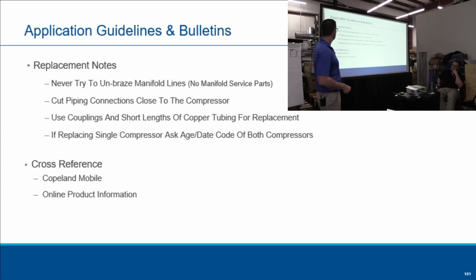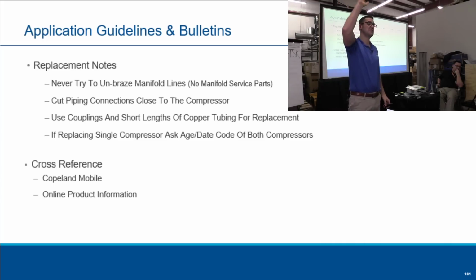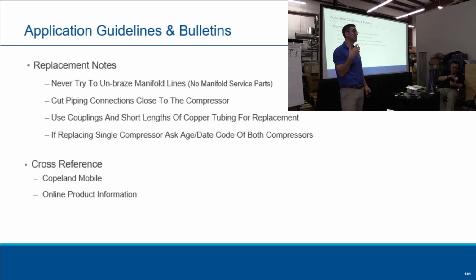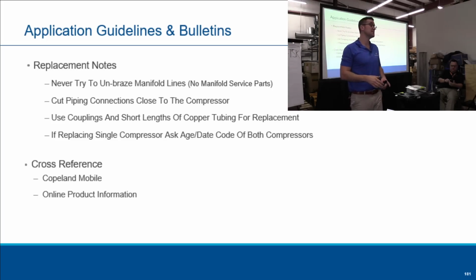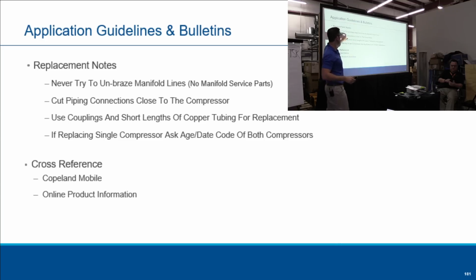Okay, I've got to try to hurry up here, but this is another thing. So you replace some tandems. If you read these AE bulletins, how many people unsweat a compressor when they're installing a new one? So a bunch of people. I've unsweated them, right? Because that's what I was taught. Copeland doesn't recommend unsweating the compressor, especially for the tandem set. Never unbraze the manifold lines.